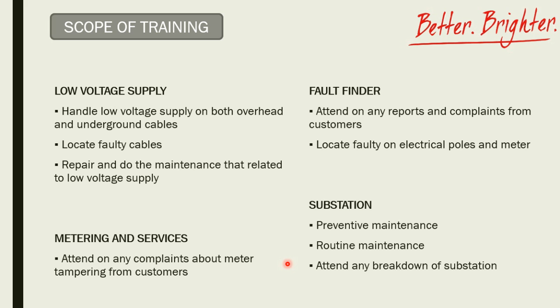Now we talk about training activities. As I told you, substation work includes preventive maintenance, which checks the cable condition from one switchgear to another, and tests the resistance of the cable between the phase cable and the earth cable. The reason we do preventive maintenance is simple: to reduce the cost of maintenance and to reduce the risk of actual or major faults.